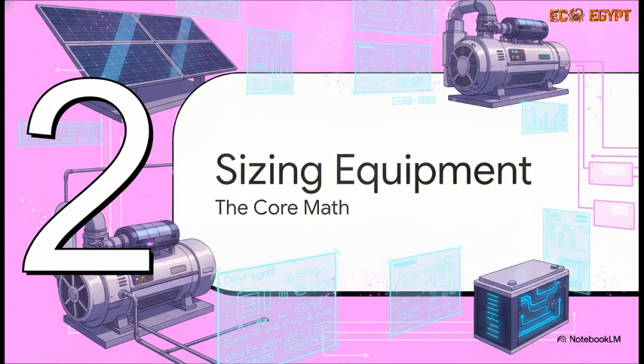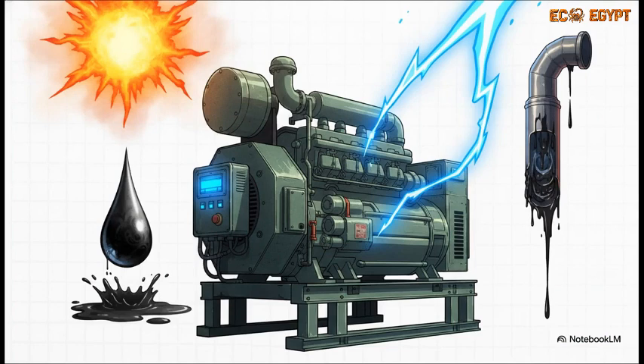Let's break down the core math. Okay, so the diesel generator is the backbone of your system, but you absolutely cannot just look at the nameplate rating and call it a day. When sizing your DG, you have to apply these 4 critical derating factors multiplicatively. You've got ambient temperature, fuel quality, nonlinear loads, and crucially, motor starting, or locked rotor current, because motors can draw up to 6 times their running current at startup. If you undersize the generator, it fails during inverter inrush. But if you oversize it just to be safe, it runs at a dangerously low load, and that causes wet stacking, a devastating buildup of unburned fuel that will literally destroy the engine over time. It's a massive balancing act.